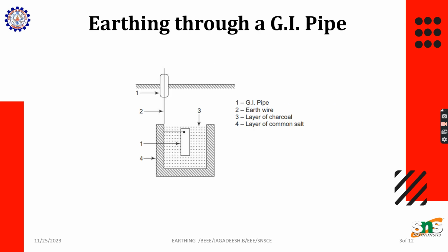Okay. So how are we going to do the earthing? As I said, it is a process of connecting a metal part or non-current carrying part of a machine, and that has to be connected to the soil. As I mentioned, it has a proper procedure to ground it. Every house has this kind of earthing. Usually the earthing will be done by a GI pipe, with a particular size and area.